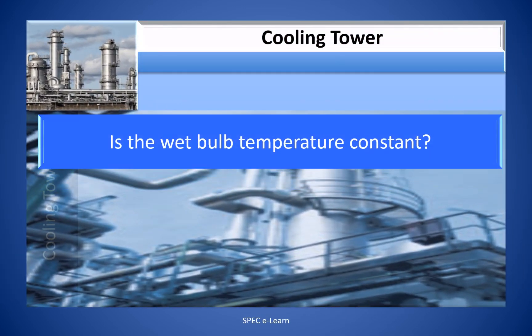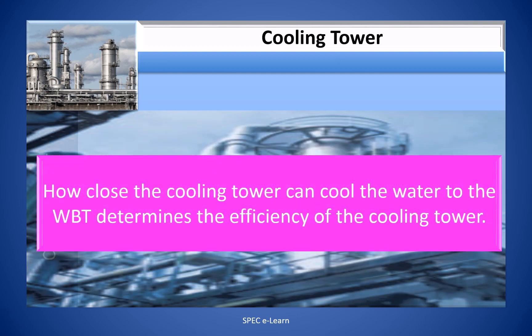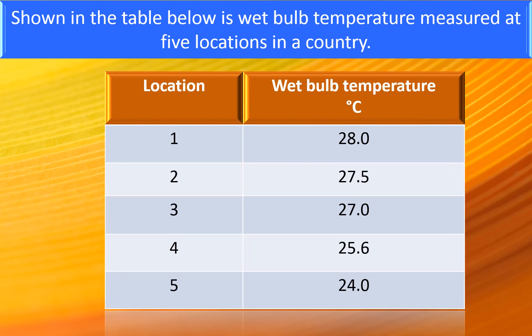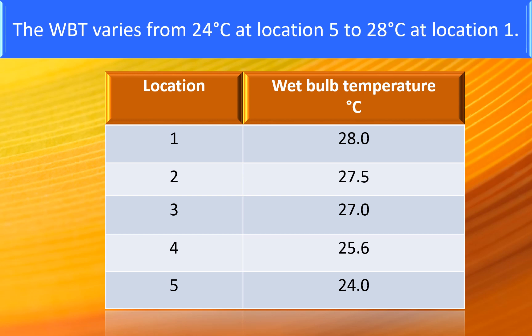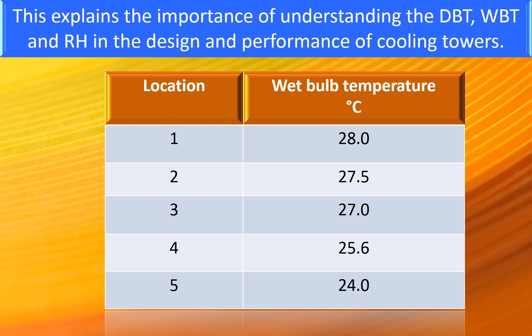Is the wet bulb temperature constant? The WBT at a particular location will remain constant for a reasonable period of time, although over the year it may vary due to seasonal factors. How close the cooling tower can cool the water to the WBT determines the efficiency of the tower. Shown in the table is WBT measured at 5 locations, varying from 24°C at location 5 to 28°C at location 1. A cooling tower designed for location 1 cannot perform the same at location 5. This explains the importance of understanding DBT, WBT, and RH in the design and performance of cooling towers.